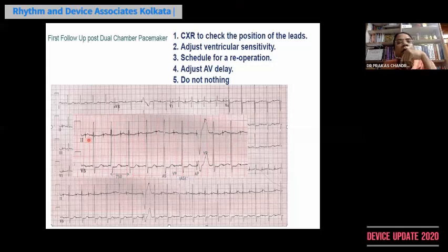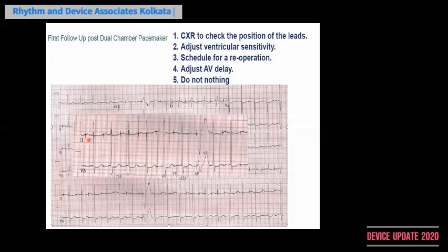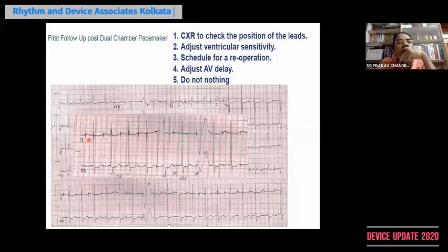Absolutely. The sensing function will not be lost. It will pace inadvertently, but the sensing function will be there. That's why, sir, the point is about a spike in the ventricle, even if the lead has reversed. So the first spike from the atrial lead, what is it expected to do? It's expected to do nothing if there is a QRS from the intrinsic ventricle, because the sensing function will be there. It will not discriminate whether it is atrial or ventricular electrical activity, but it will sense.